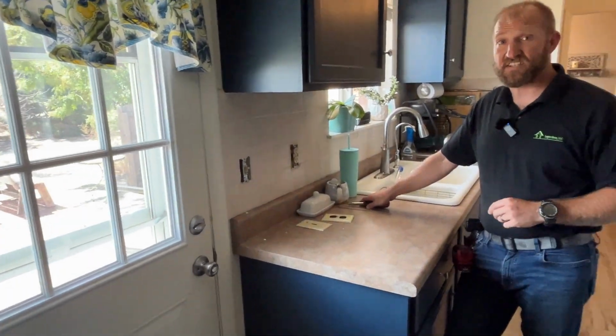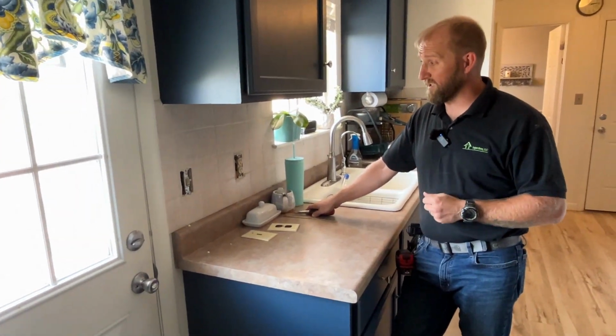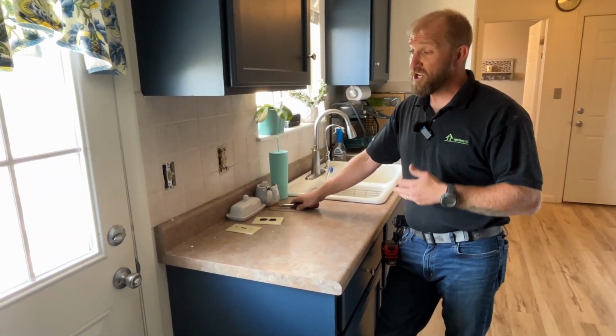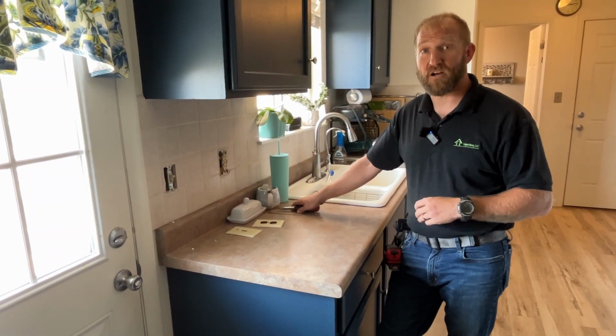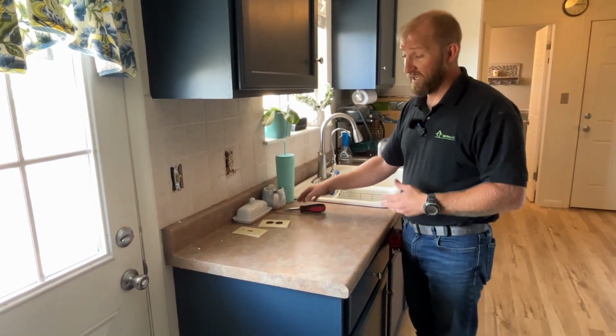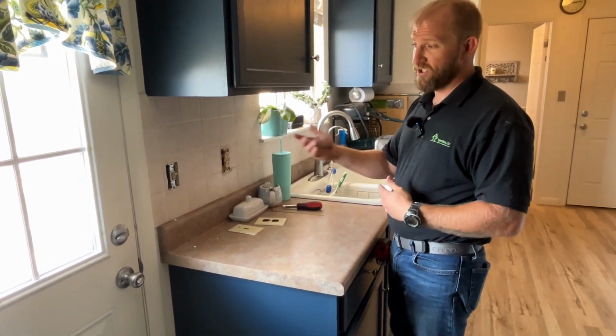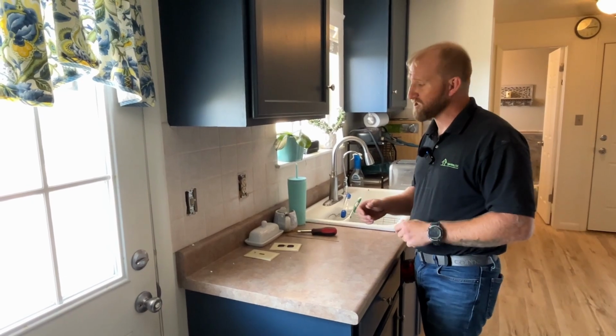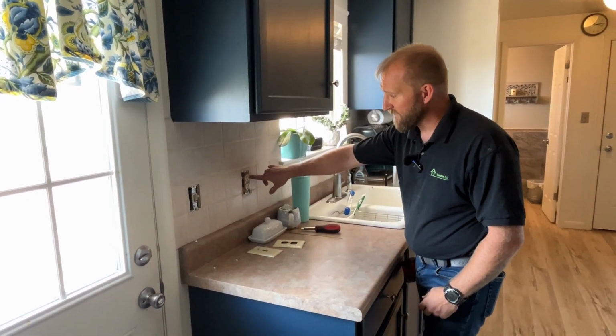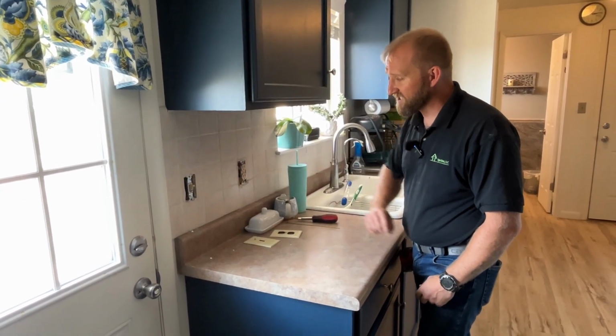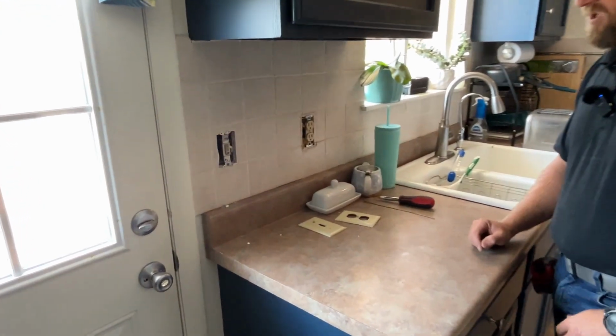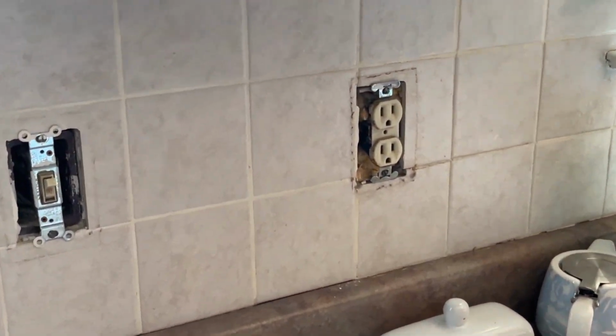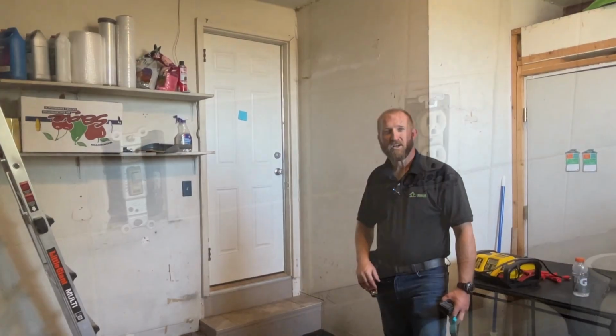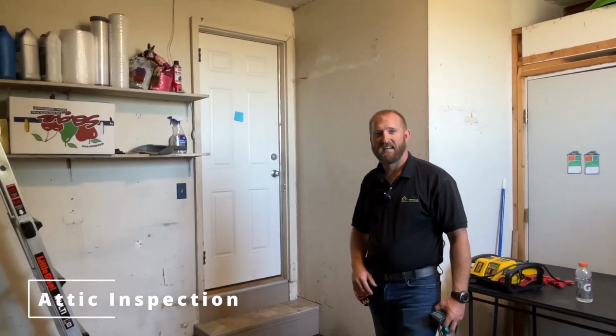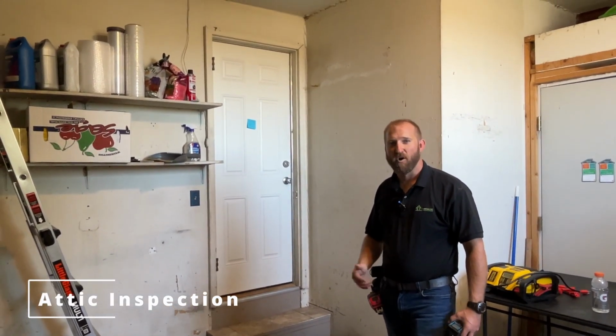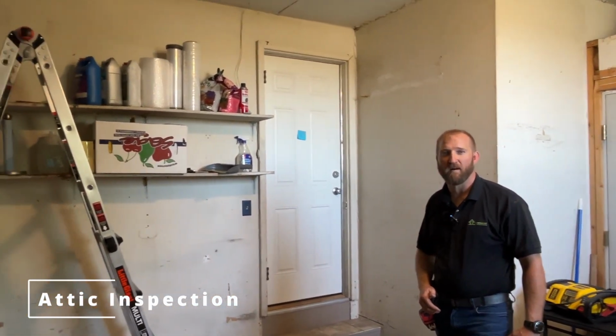So here in this instance, we're checking the outlets and switches. You may wind up coming across some other health and safety concerns. It may take more than one outlet to get your depths and your insulation levels. So in the kitchen here, they put a spray foam inside of the box, which is not good to be up against the wiring. So we're going to go ahead and check out the attic and the insulation levels up there and go over the things that you're going to have to look for up in an attic space.